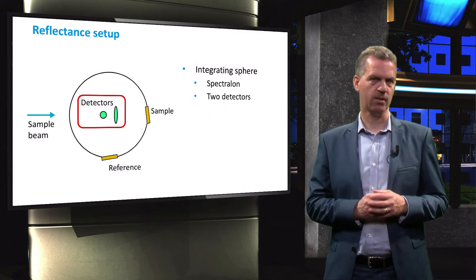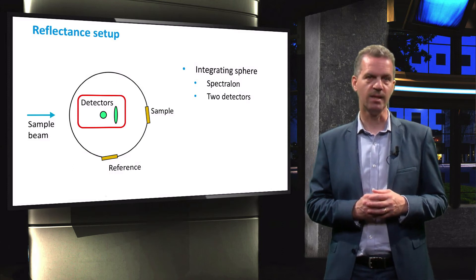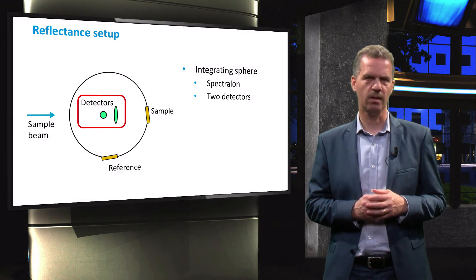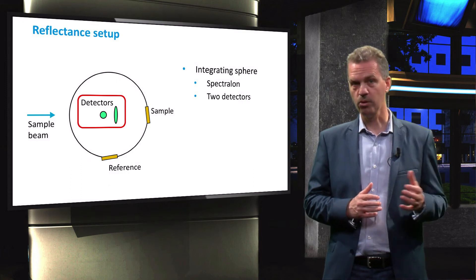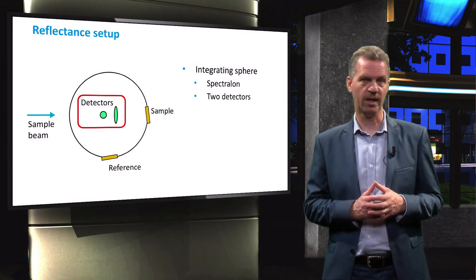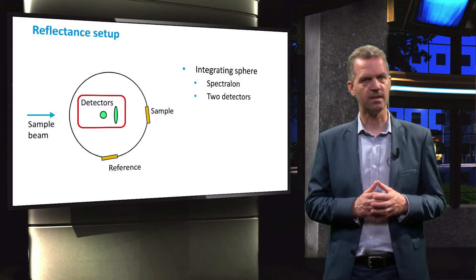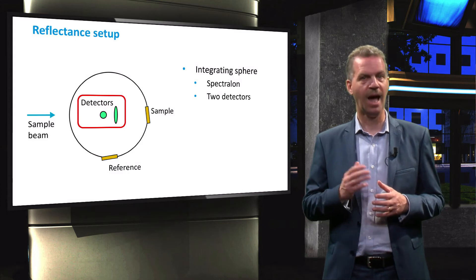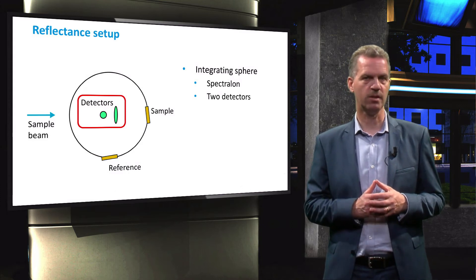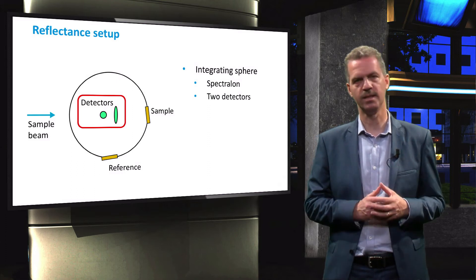Two different detectors are located on the bottom of the sphere, that each measure light intensity in different wavelength ranges. A photomultiplier tube is used for wavelengths up to 860 nm, which is a highly sensitive sensor for ultraviolet and visible light. And a lead sulphide photodetector is used for measuring the photon flux at wavelengths above 860 nm.